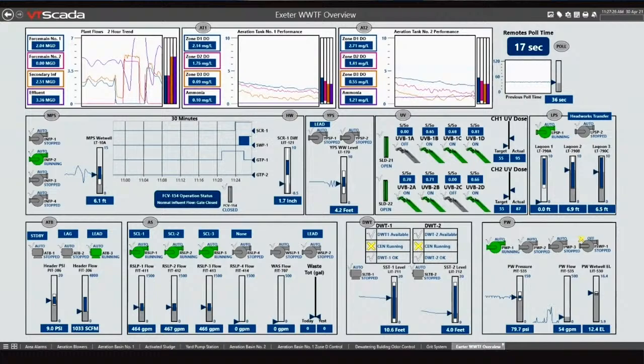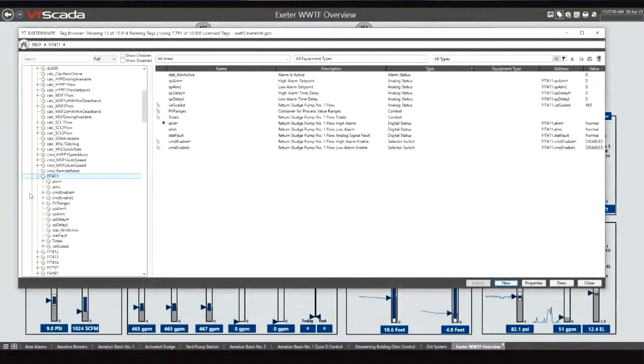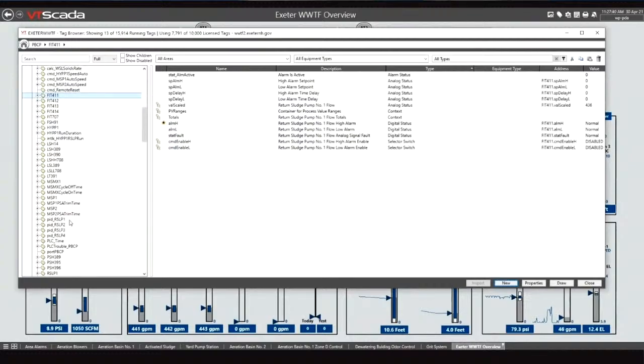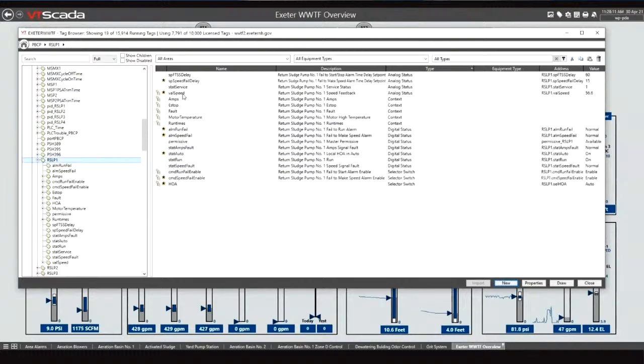So for one example, we have a tag type that we call motor, and that has 81 descendants in it, 81 tags. And by linking by a single tag name by the parent, what we have is the ability to grab 81 data points with a single tag name. And what that does is obviously streamlines database development, eliminates errors because we have the template that we already know works that's going down to the PLC and grabbing the right information, makes commissioning very, very easy. So here's an example of a motor that we also have.